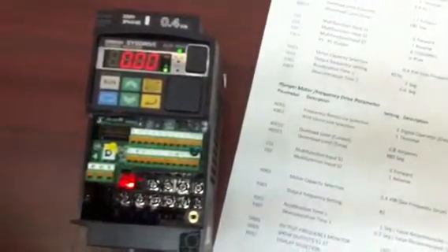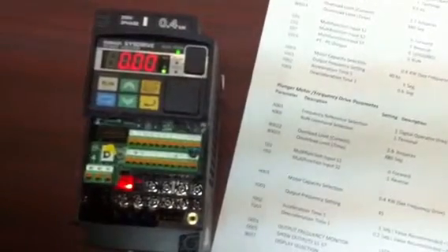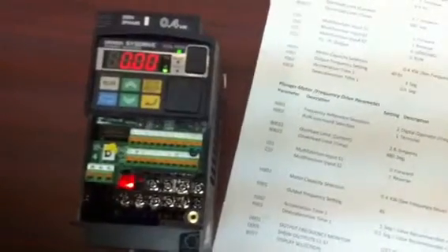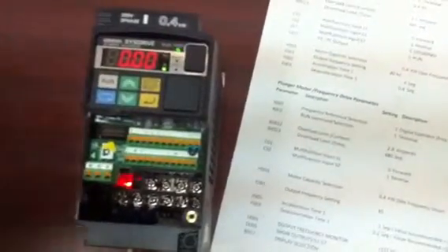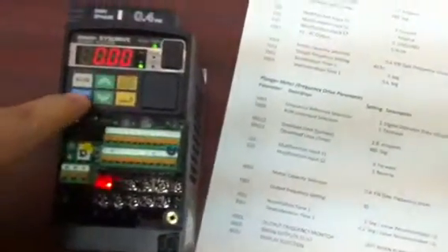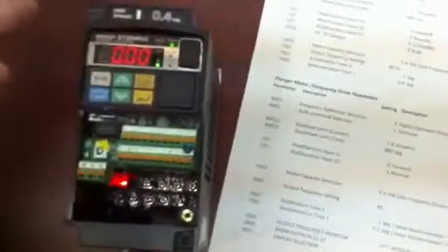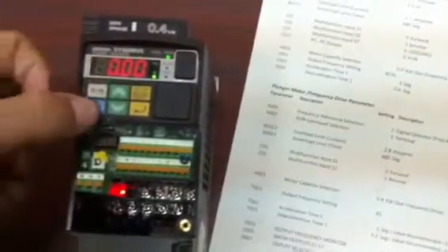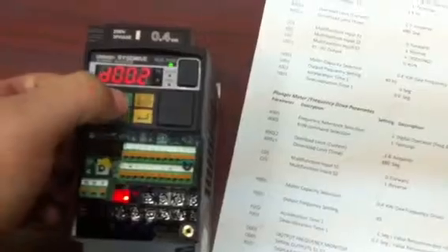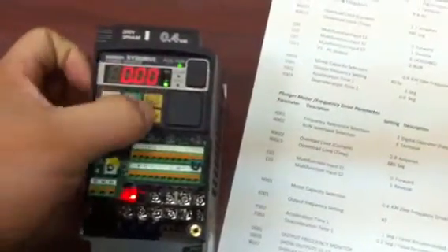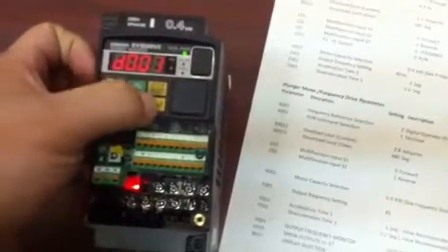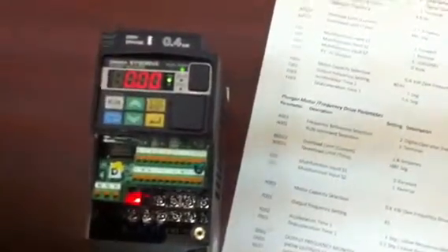Usually, if there's any problem with misalignment on the table or the chain rubbing something, you usually get some kind of extra current draw, and that's what drives this issue. So by having this as D002 and running, it's going to give you that screen of the amperage, or the hertz speed.